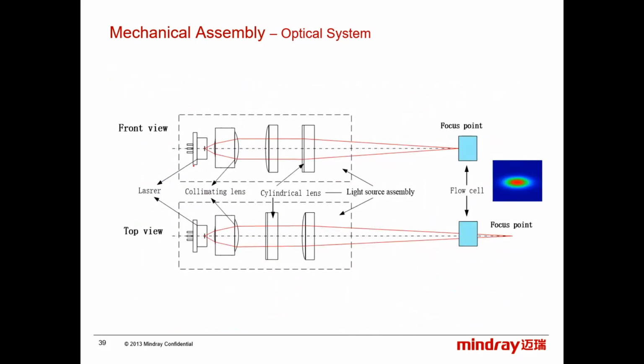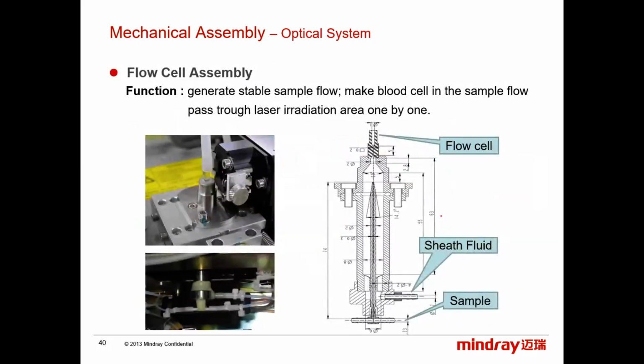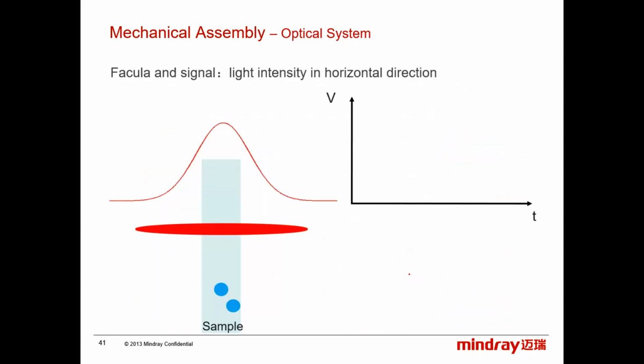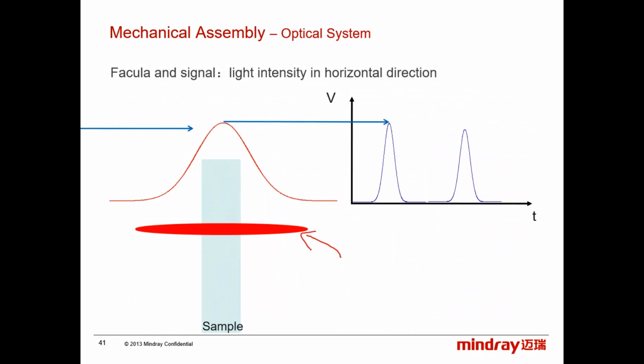This is the front view, the focus point in the flow cell, and this is the top view, so you get an elliptical shape. This is the flow cell assembly. We have the sample injection here and the sheath fluid injection here. In case of a clog or some issue with it, you need to replace the whole optical assembly. As you see here, this is my laser facula.